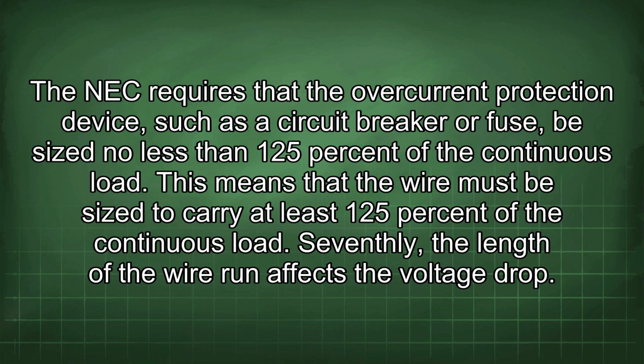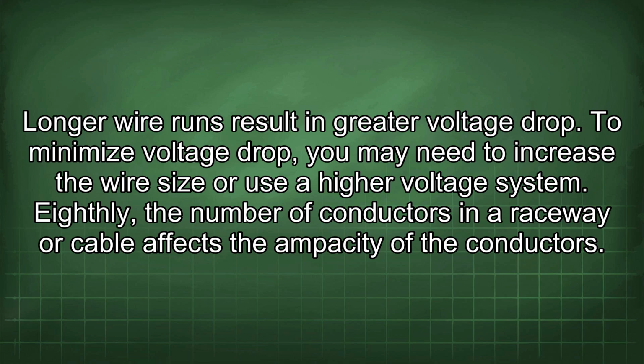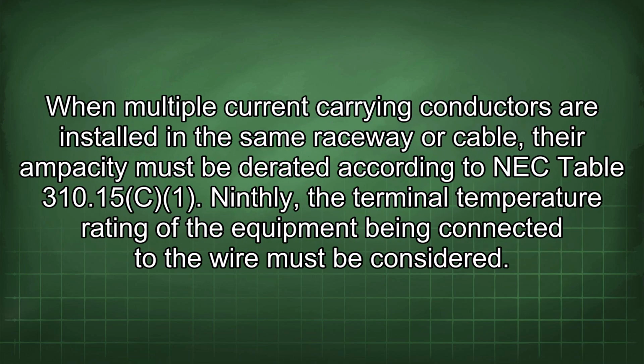Seventhly, the length of the wire run affects the voltage drop. Longer wire runs result in greater voltage drop. To minimize voltage drop, you may need to increase the wire size or use a higher voltage system. Eighthly, the number of conductors in a raceway or cable affects the ampacity of the conductors. When multiple current-carrying conductors are installed in the same raceway or cable, their ampacity must be derated according to NEC Table 310.15. Ninthly, the terminal temperature rating of the equipment being connected to the wire must be considered.